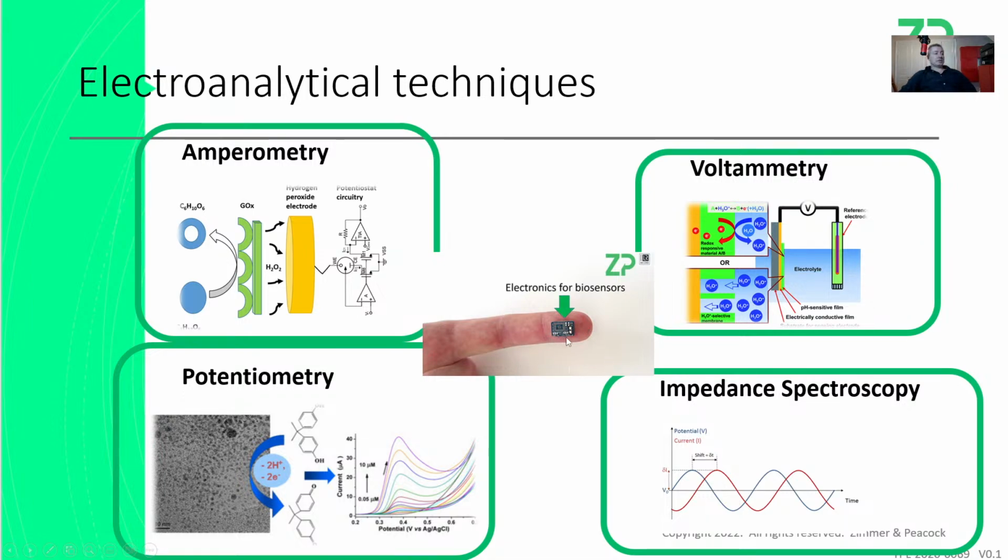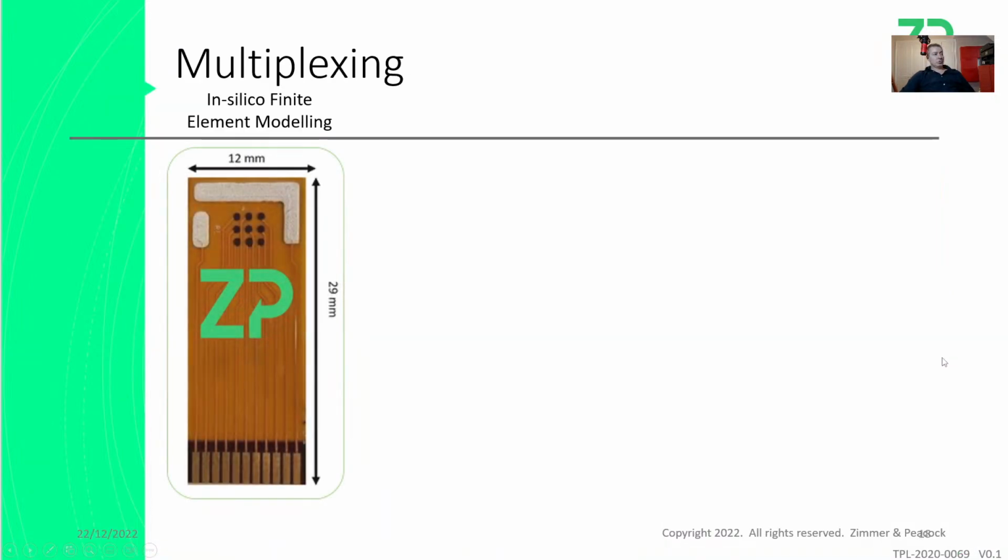It's also worth saying that these techniques are not excluded if you're doing IVD or wearable sensors. This is our most recent wearables board. It can do everything, well, everything's a big statement, but EIS, voltammetry, amperometry, potentiometry. The world has really moved on. This particular inquirer is also quite interested in using several working electrodes in the same sample. So we do have that technology.